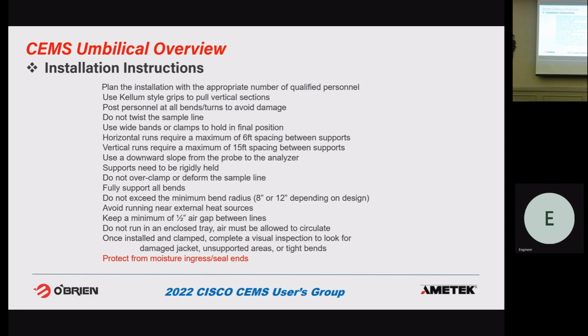And then, fully support all bends. Bend radius 8 to 12 inches. In general, for a 2-inch bundle or smaller, 8-inch bend radius. Anything above that, 12-inch bend radius. Air gap. We need a 1/2-inch air gap between umbilicals being run, just to get good air circulation.